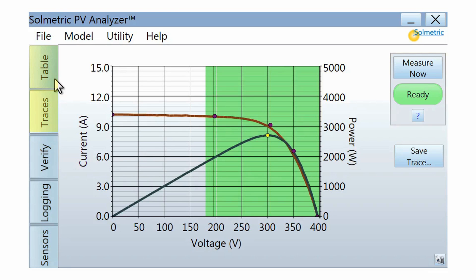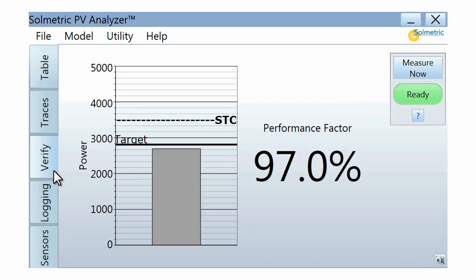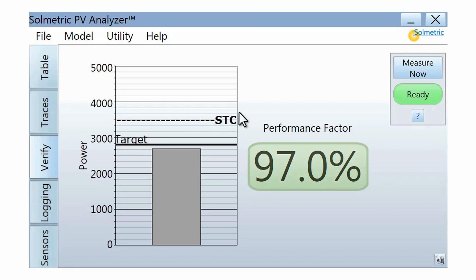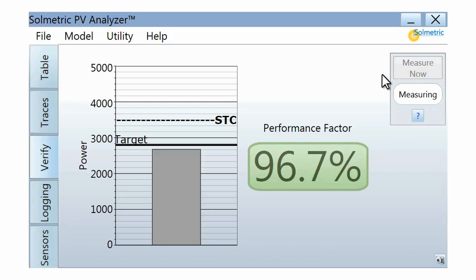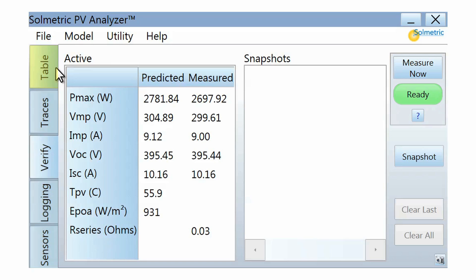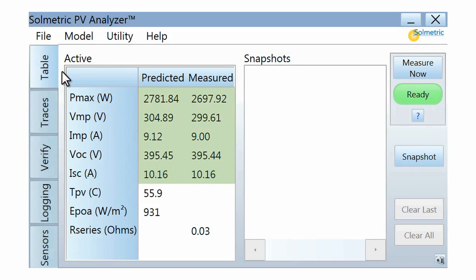The results can be viewed in various formats. The Verify tab shows a simple percentage value that represents the measured power output as a percentage of the power predicted by the performance model. This percentage is called the performance factor, and it provides a quick and simple method of performance verification. The Table tab displays the measured and predicted parameters, including short circuit current, open circuit voltage, and the maximum power point.